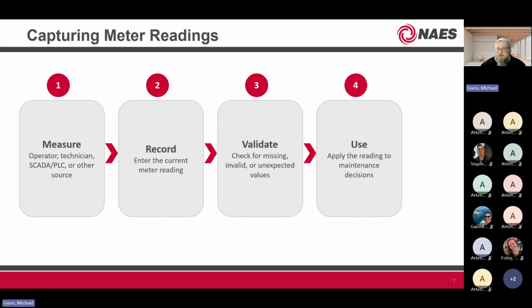I've seen so many times where someone put in wrong readings, and you'll see on a line chart an abnormally low DP because they put 0 in. We can investigate that to see if it was an actual issue or a data capturing issue.